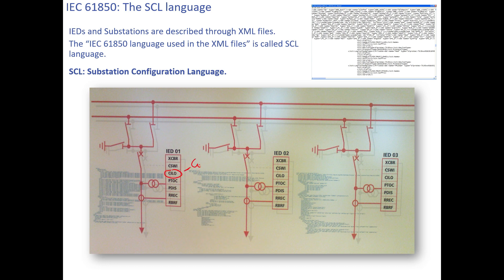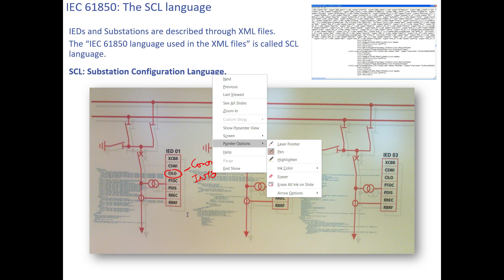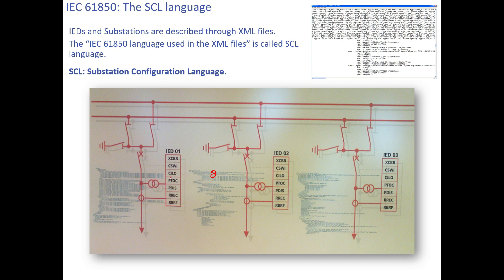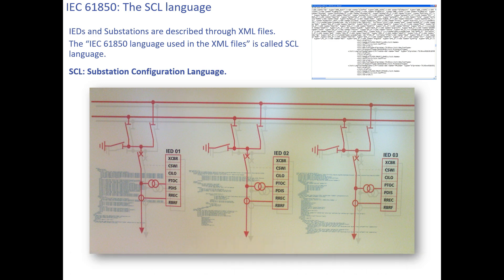CILO is for interlock — C is for control and ILO is for interlock. All logical nodes are already defined in 61850. Any logical node starting with P is related to protection, such as distance protection, time-delayed overcurrent, or instantaneous overcurrent. Any logical node starting with R is for protection-related functions. Protection-related functions may be REC for autoreclose or BRF for breaker failure.